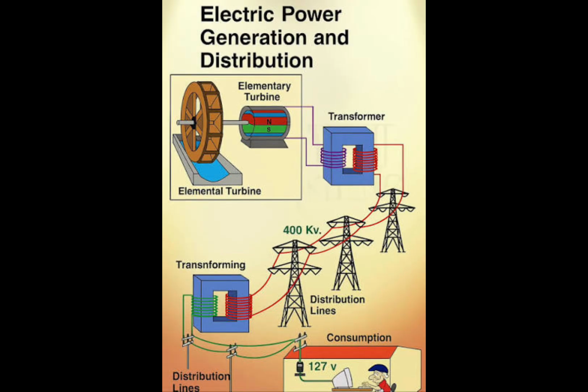To understand a substation, you must first understand the physics of transmission. To move power efficiently across vast distances, say, from a wind farm in the Texas Panhandle to the suburbs of Dallas, engineers must crank the voltage to extreme levels, often 345,000 or 500,000 volts. High voltage means lower current, which minimizes the energy lost as heat along the wires. But you cannot feed 500,000 volts into a city block. It would instantly vaporize local distribution lines. The power must be stepped down.